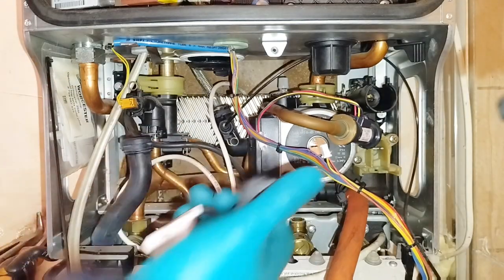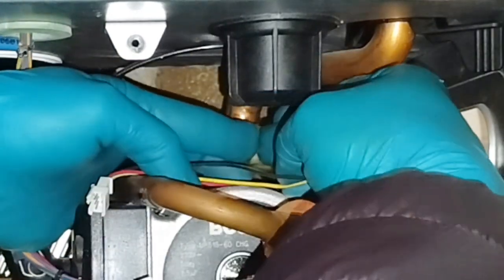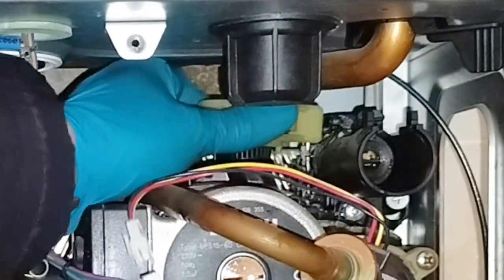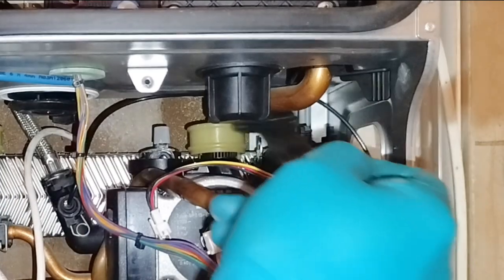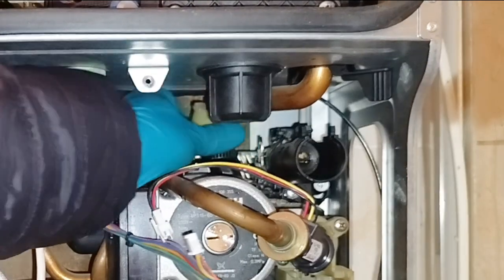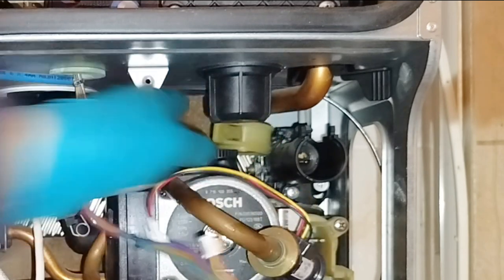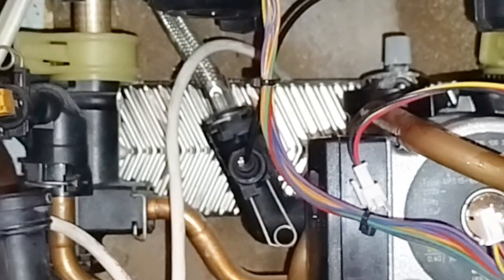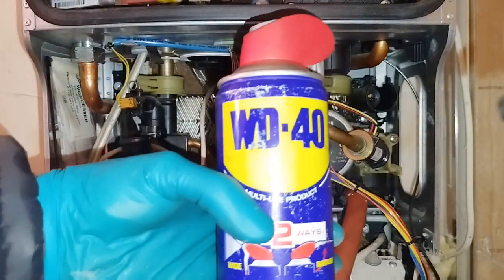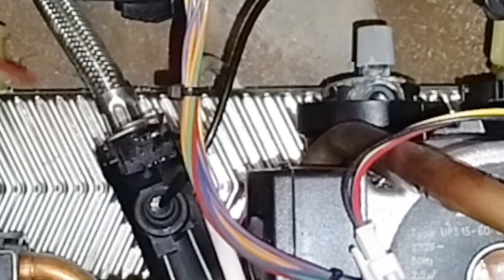And then undo the locking nut on the return, the primary return. After that, we've removed the pump's cable to be able to further turn the locking nut on the primary return. We turned it to a 3 o'clock position, then it releases the joint. I've just wedged a spanner, or anything long enough, to lever the pipe upwards to get release from the top of the pump. Now the two clips which are holding the expansion vessel's hose and the pressure gauge's hose in, we've released the two clips, and then I always use WD-40 on it before I start to attempt removing it.